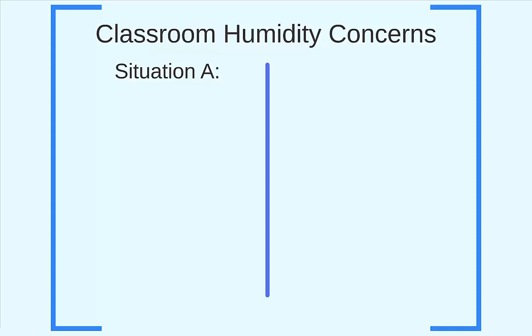Here at AFIT, when classes are in session, we can have some pretty jam-packed rooms. Many of our classrooms have an exterior wall, and since we are in Ohio, there are times when the cooling requirements for the space are quite high and times when they are quite low, even when fully packed with students. In a classroom setting, however, 35 students breathing is going to produce about the same amount of moisture gain in a space regardless of how large or small the sensible cooling requirements for the space are.